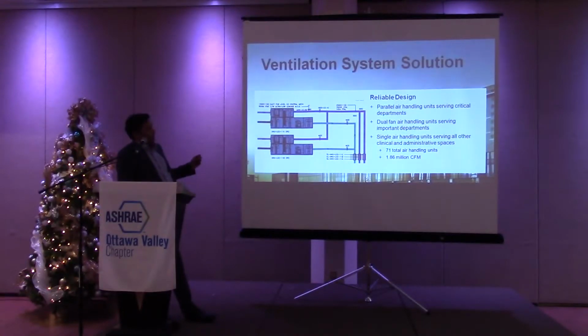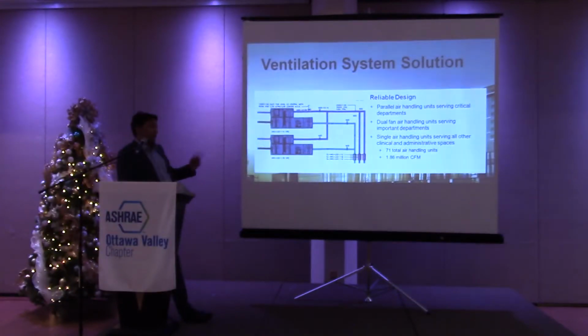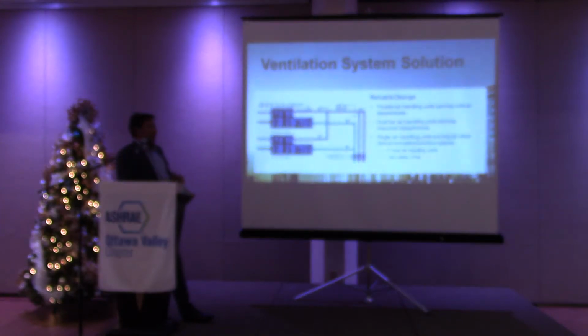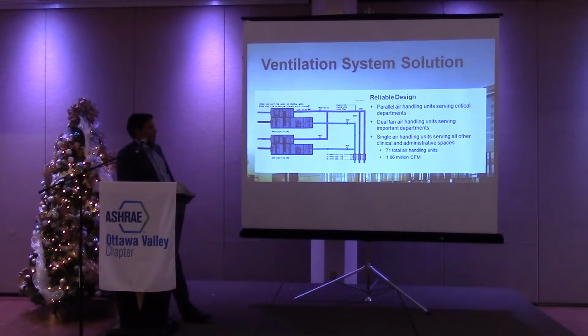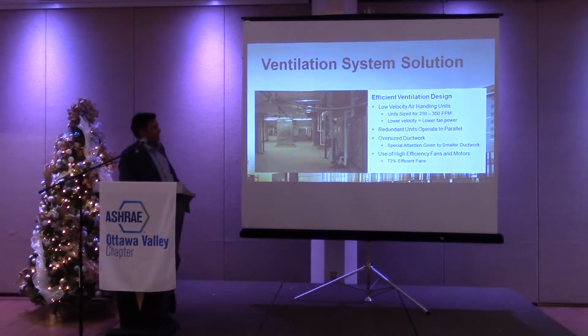You had full redundancy and full backup. Where we had less critical departments, like a food service area that might run 24/7 but is not as critical for patient care, those would have dual fans. So we'd have one air handler unit with 2 fans in it, each sized to be able to handle the load. And then for administrative spaces where people go home at night and maintenance can be done at night, in those cases we had single air handler units. So 71 total air handling units, not including the small ones, and 1.86 million CFM. I doubt in my career I'm going to surpass that size of air handling system.